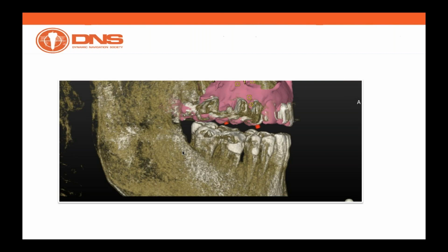And we could achieve that by means of tracing, by introducing what we call a tracer, which is nothing more than a contact scan tracer, which allows us to contour the surface of a minimum of 3 teeth, and therefore generate a 3D mesh, which the software matches with the 3D rendering of the patient.